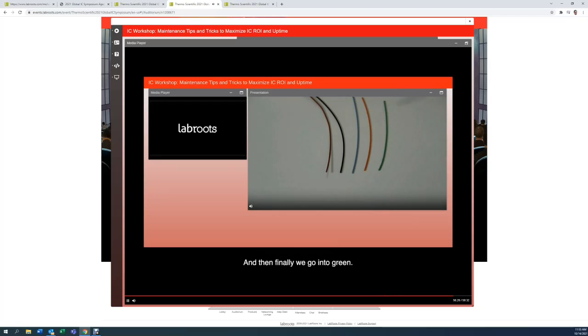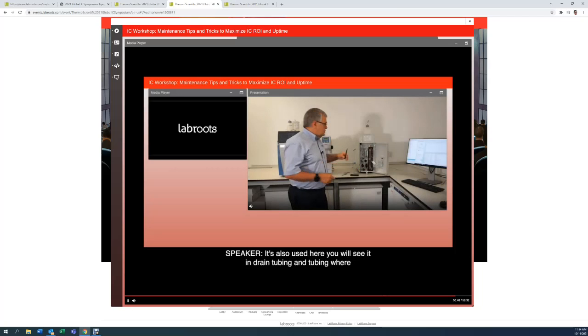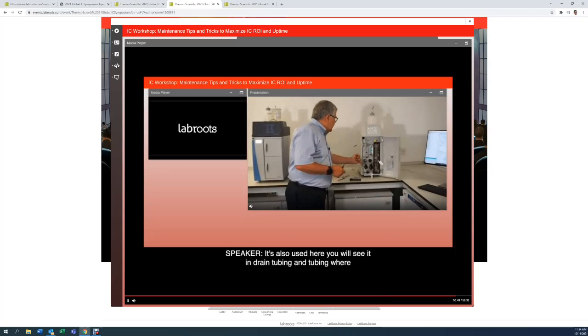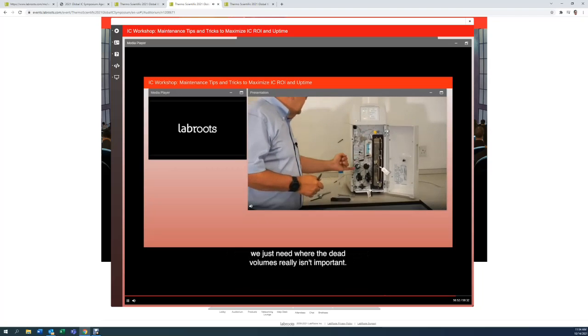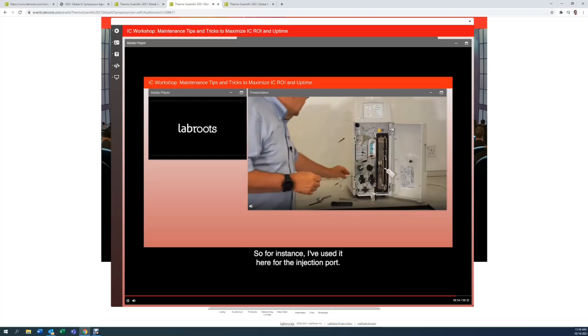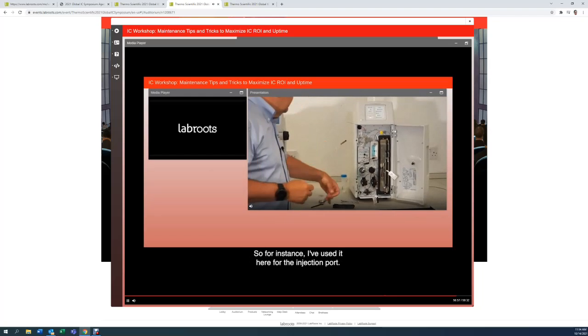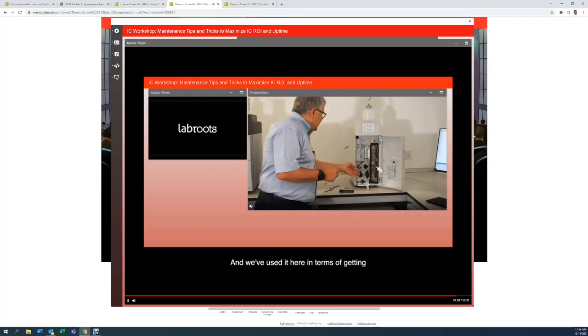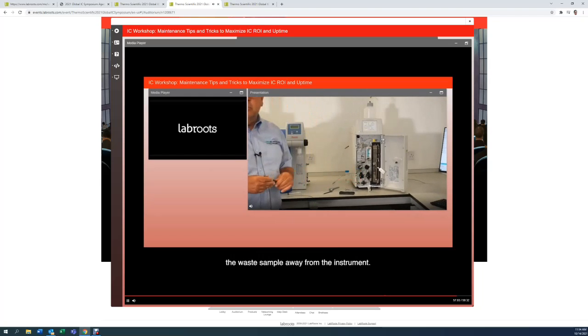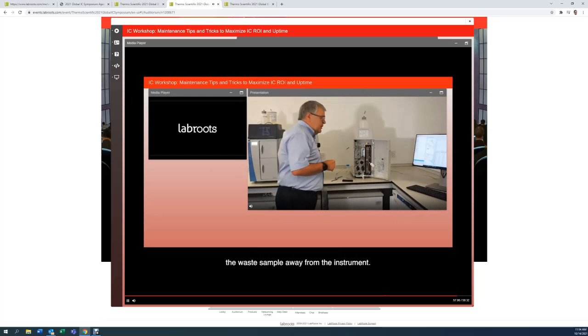And then finally we go into green. Now a green tubing is used in two places. One, it's used for very high volume injection loops, 100 microliter, 200 plus injection loop volumes. But it's also used, and we've just cut back to the instrument now, it's also used here, and you'll see it in drain tubing and tubing where dead volume just really isn't important. So for instance, I've used it here for the injection port, and we've used it here in terms of getting the waste sample away from the instrument.